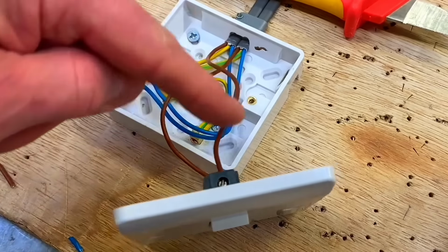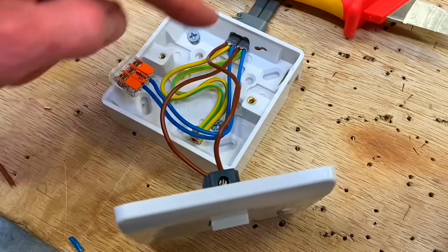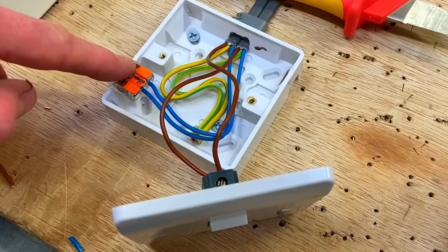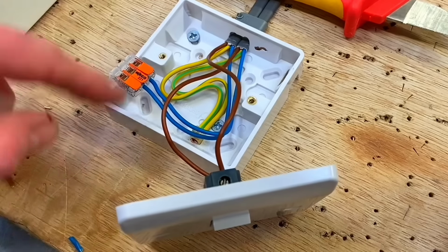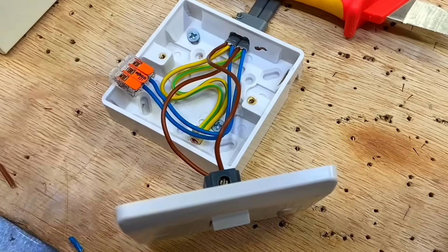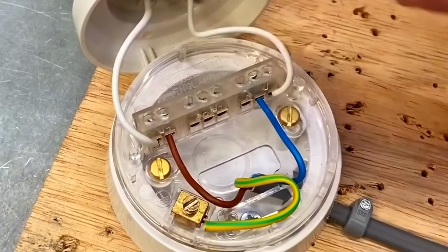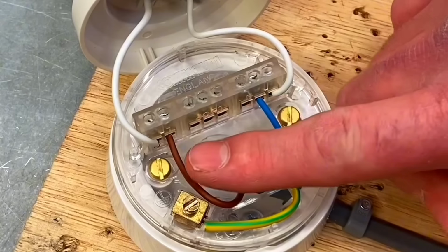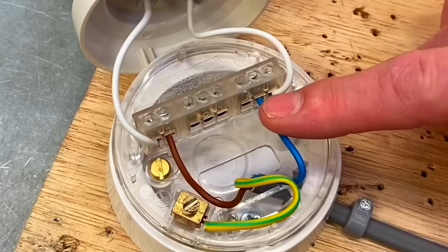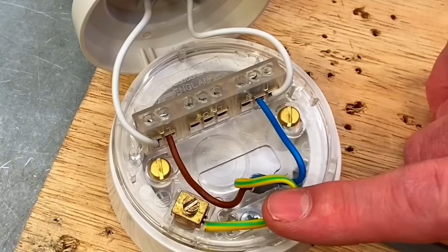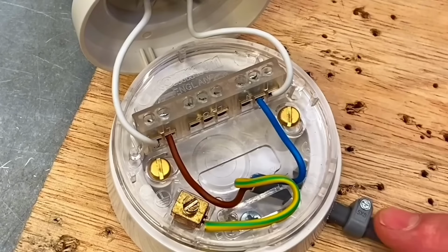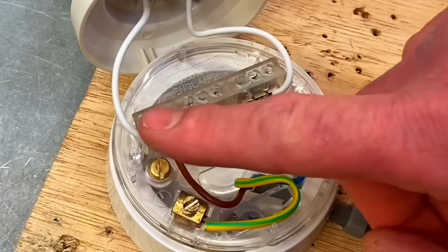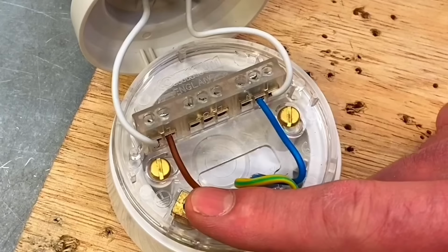So we've got our permanent line coming down into common. We've got a switching line going back out to our light fitting. We've got our two neutrals connected together in a Wago connector block, and our CPCs are secured in the back of the box because it's a fully insulated box and switch. I've used a conventional 3-plate one, so we've got the loop-in terminal in the center, which is no longer needed. We've got the switching line coming from the switch, the neutral coming from the switch, and the CPC also coming from the switch. So this cable here brought in the switching line, neutral and CPC, and is connected neutral across the lamp, switching line across the lamp, and the CPC secured in the back of the actual fitting itself.